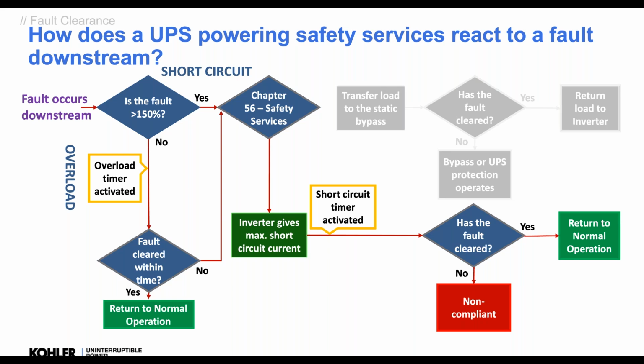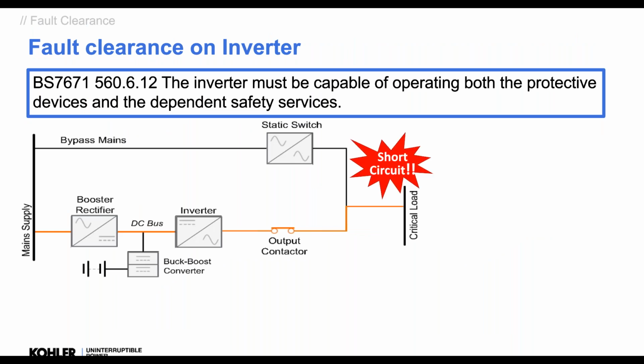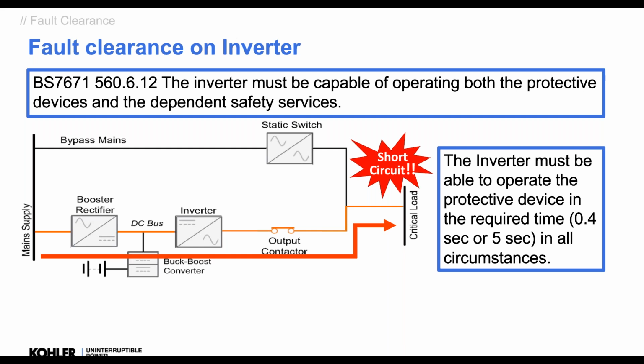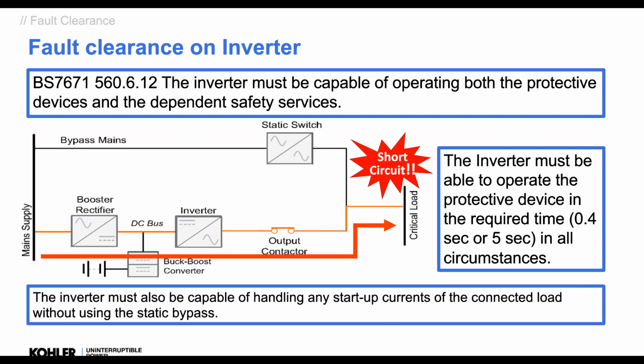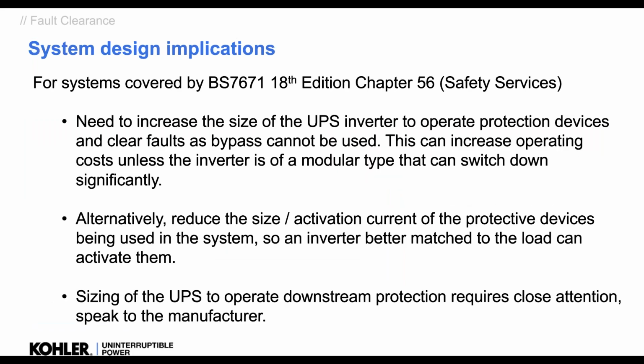So when the UPS is online, we have an output short, and we need to clear those breakers in the required time, depending if it's a final circuit or sub main. Typically, we're tripping final circuits in 0.4 of a second. And we have to be able to start those loads as well. Typically in hospitals, everything's running, everything's fine. What we also see in a lot of life safety applications is we have to put the UPS on and then start up the load. Could be a lot of motor load, things like that, that we have to be able to start on the inverter when it's needed. So we have to make sure the UPS can do it.